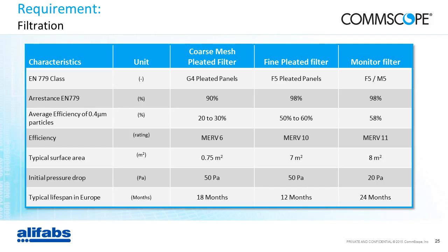The surface area is 8 square meters, and that's one filter per fan. So on the monitor 9 with 2 fans, you have 2 filters, which means you have 16 square meters of filter area. And the pressure drop on day 1, which is very low, allows our system to keep performing and delivering the energy efficiency that it provides on day 1 for a lot longer than any other systems.